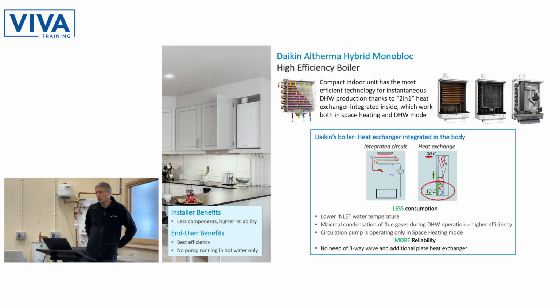So it's a high efficiency boiler. It's a 2-in-1 heat exchanger. So it's actually got a separate circuit in the heat exchanger for the heating and the hot water. So we've got a number of advantages to this. Firstly, you've got a lower water inlet temperature going into the heat exchanger for hot water and heating, so that's maximising the efficiency of that. The circulation pump only needs to operate in space heating mode, so there's no secondary circuit, there's no secondary heat exchanger, which also helps with reliability and noise if they're using hot water at night. Less components, high reliability, so that's a good reliable boiler, this one. So you can fit that with confidence, and you know that it's going to keep working.